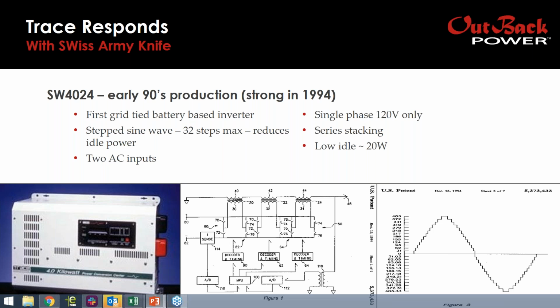One was it had two AC inputs, so you could have a generator and a grid input. So you could charge your battery from grid, or you could charge your battery from a generator. It also only produced single phase AC, and it could be series stacked. So you could stack two inverters to get 120/240. It had fairly low idle power of only 20 watts.